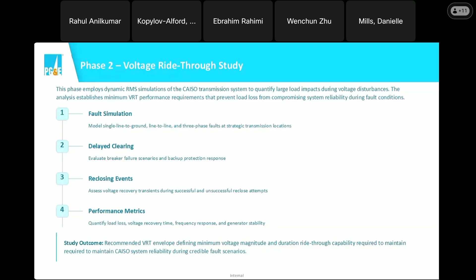The objective is to really determine the voltage time envelope that is necessary to prevent any disturbance-driven load disconnection from materially degrading any of our system recovery. It's not really an analogy for the generator ride-through curves, but this is ultimately what we want to try and translate this into. That's a common theme in everything you see in other utilities and ISOs as well. If you can move to the next slide, please.